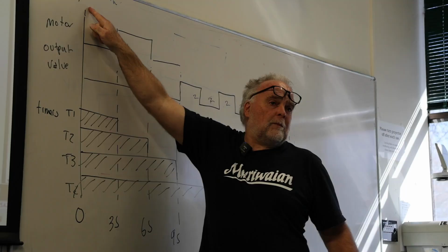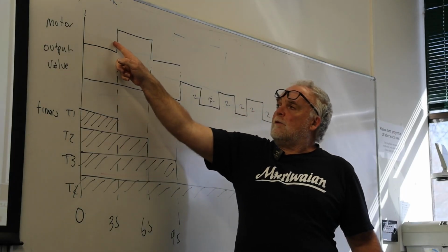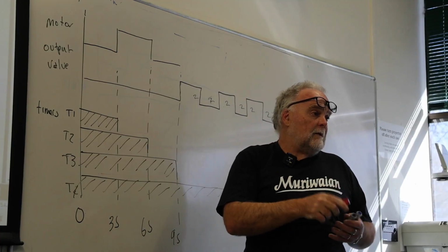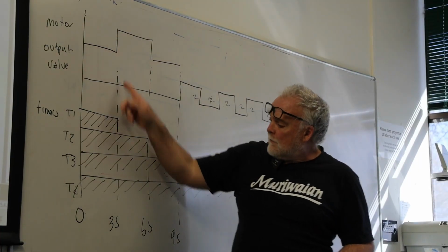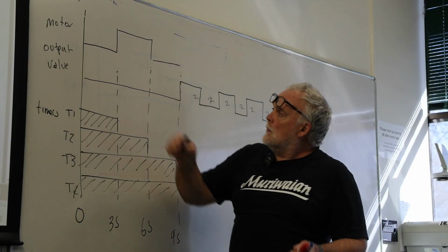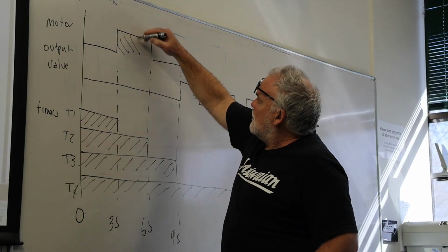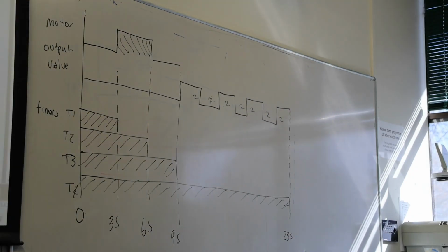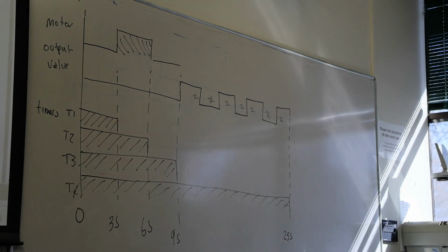Once that float switch happens, it says to pause for 3 seconds and then run our mixer motor for 3 seconds. Is that right? Everyone's happy with that, eh? So I put some times down here. Wait 3 seconds, run our mixer motor. Here's our mixer motor there, on. And then it says to wait 3 more seconds. And then open the output valve, 2 seconds on, 2 seconds off, 2 seconds on. Do that 4 times.